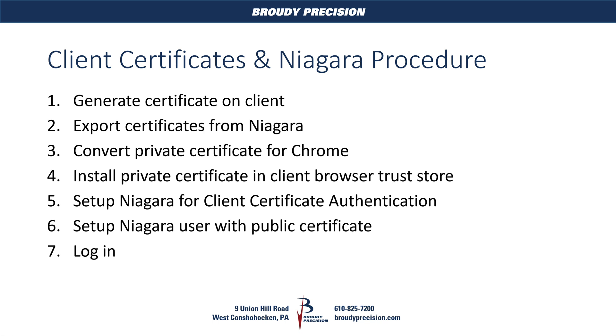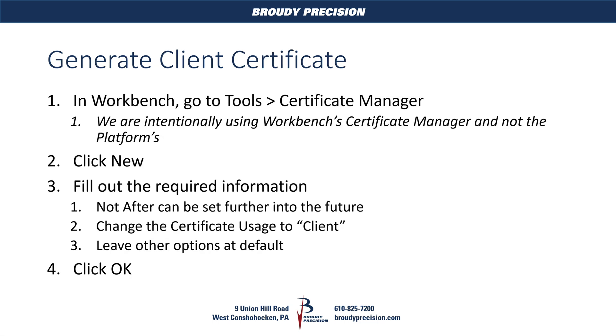The client certificates in Niagara procedure is a little bit in depth. It requires you to generate a certificate on your client side, export certificates from Niagara, and convert those private certificates for Chrome because Chrome requires a specific file type. Then you'll install that certificate into Chrome's trust store, set up Niagara to use client certificate authentication, and set up your specific user to look at a specific public certificate that matches up with your private key living on the client itself.